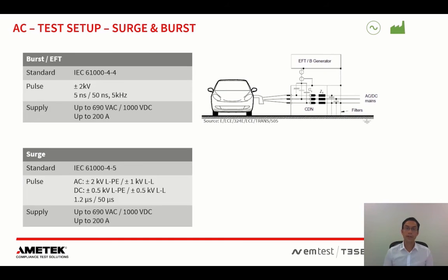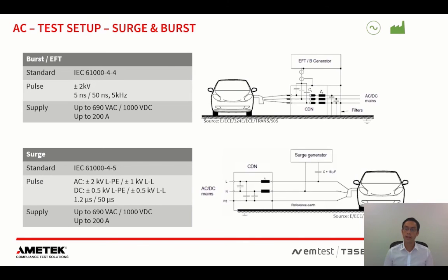Now the surge test is a very similar test, but with another pulse. So it's according to IEC 61000-4-5. The test levels are for AC charging plus minus 2 kilovolt for line to protective earth, or plus minus 1 kilovolt line to line. If the car is charged in DC mode, it is 0.5 kilovolt line to protective earth or 0.5 kilovolt line to line. And the test setup is very similar. So we have again a coupling decoupling network, which is shown here on the left. Then you have a surge generator that generates the typical surge pulse, and it is coupled through an 18 microfarad capacitor on the DC or AC line.